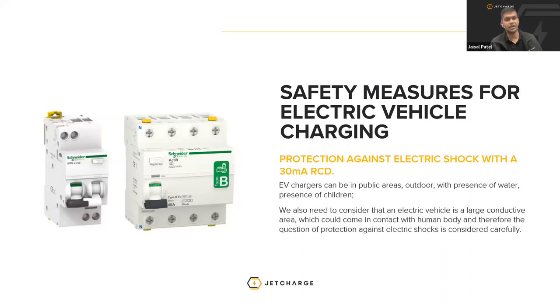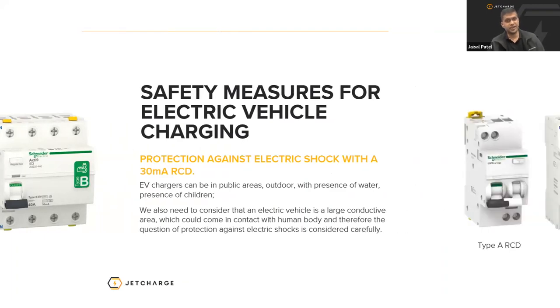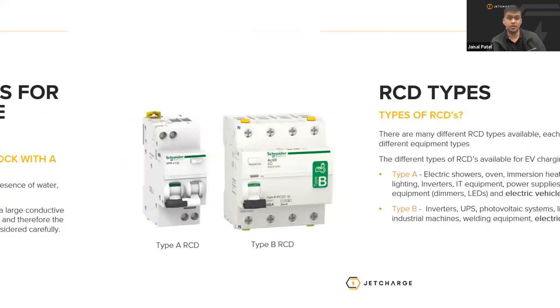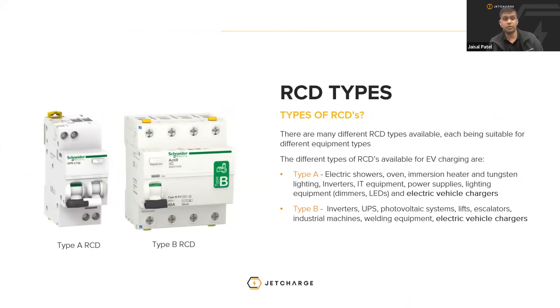Next slide, please. A 30 milliamp RCD comes in a few forms, but typically for EV charging, we use two types of RCDs: what's called a type A RCD, which is typically used in a wide variety of electric showers, ovens, immersion heaters, and tungsten lighting. And type B RCDs are mostly used in inverters, UPS, photovoltaic systems, lifts, etc. How they differ, please, next slide.